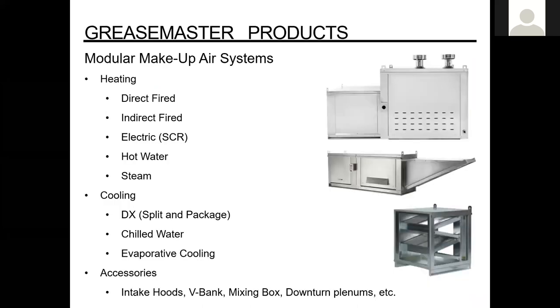With that, I want to talk a little bit about some of the makeup air opportunities that Greasemaster provides. They have a modular system. So you'll have your air handling unit or your blower, and then you can add different kinds of heating. So you can do a direct fired unit, indirect fired, electric, SCR, so fully modulating. Don't do too much of this, but I have seen hot water and steam. I haven't seen a steam system for a few years. But the hot water we have done.